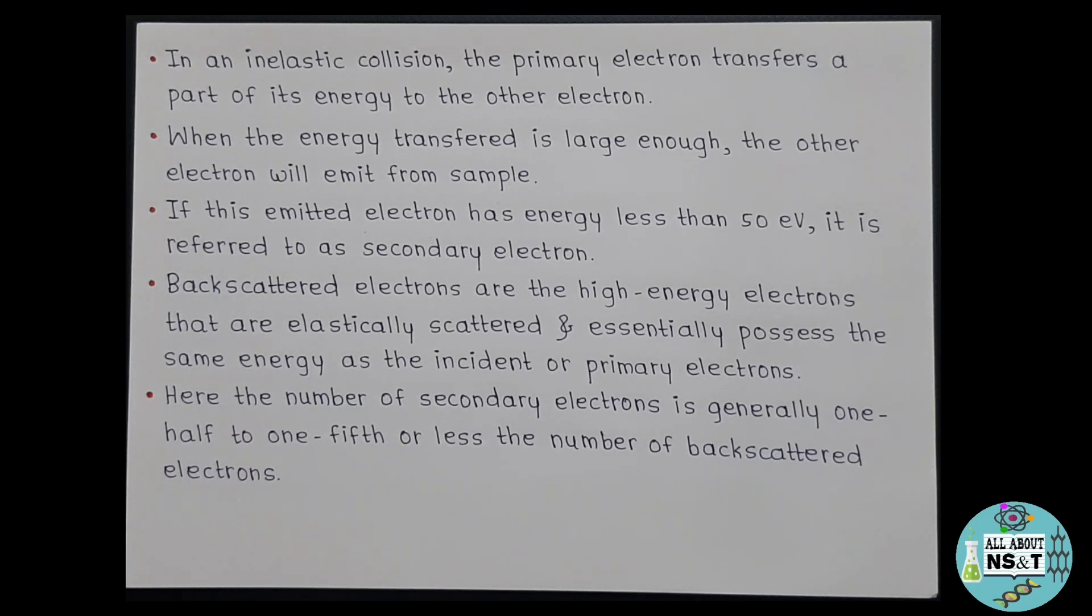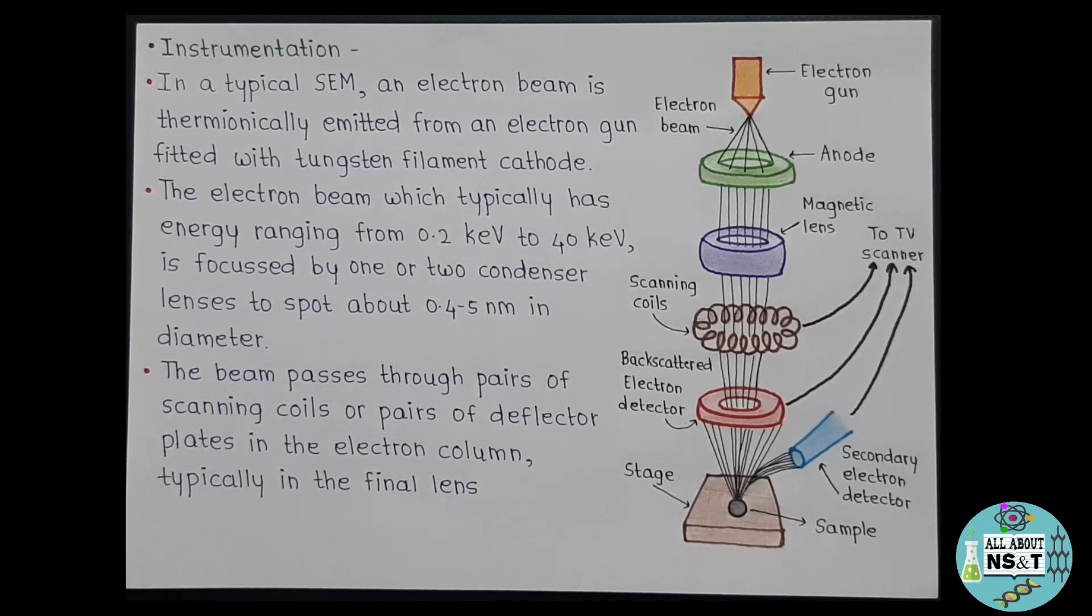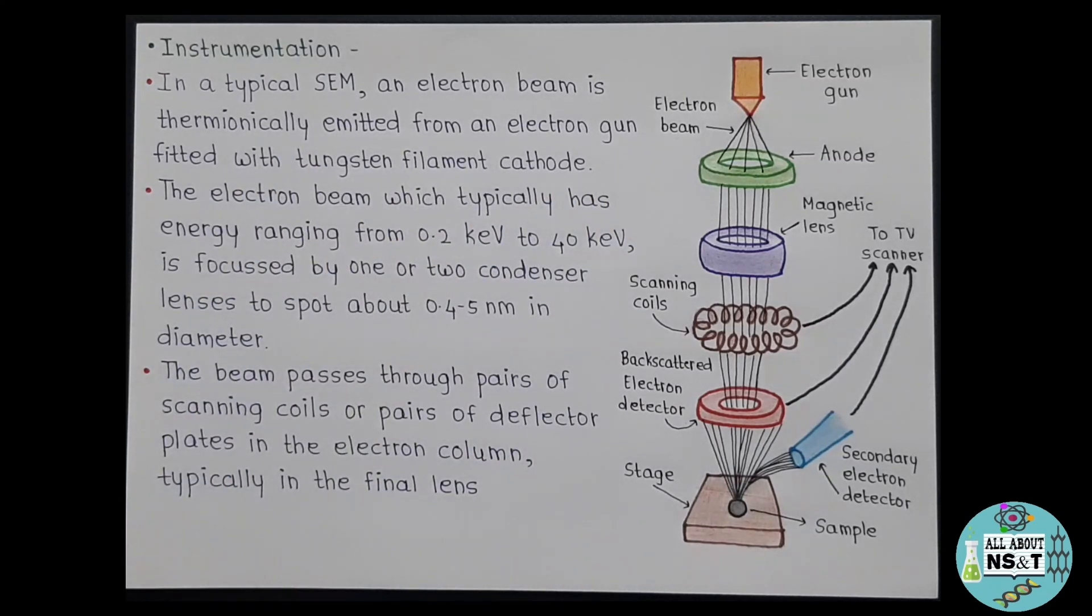So this was all about the basic principle of SEM, and now let's move towards its instrumentation part. So here is the diagram that shows essential parts of a scanning electron microscope. In a typical SEM, an electron beam is thermionically emitted from an electron gun fitted with tungsten filament cathode. So here tungsten is mostly used in guns because it has highest melting point and lowest vapor pressure of all metals, allowing it to be heated for electron emission, and also it is cheap. The electron beam, which typically has energy ranging from 0.2 kilo electron volt to 40 kilo electron volt, is focused by one or two condenser lenses to spot about 0.4 to 5 nanometers in diameter.